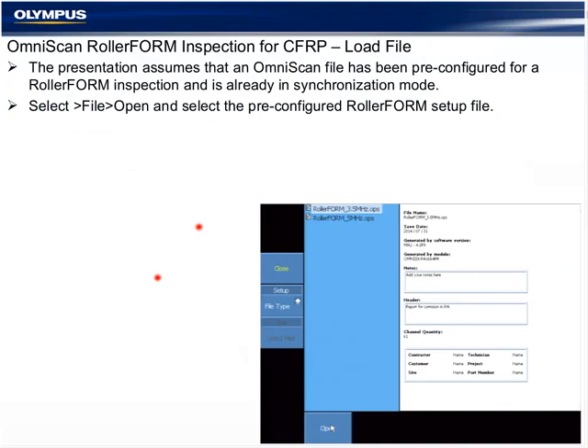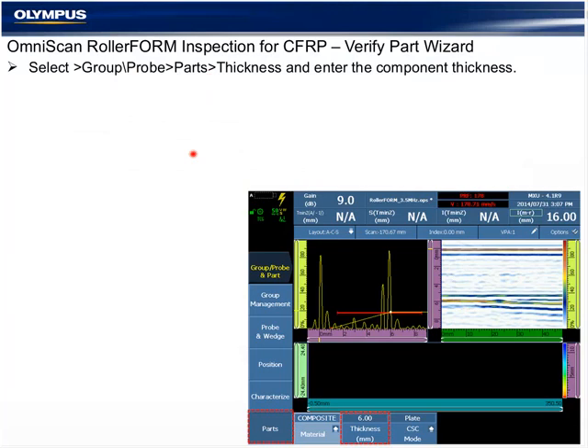Again, you're going to be provided default setup files with all of these parameters configured. This third presentation is designed to be used with either one of those files we've provided or the file you would have just created up to this point. On the OmniScan file name area, press and hold, or go to File, Open, and under the Setup filter we'll see the various setup files for the RollerFORM or the ones we've already created ourselves. We initially input the part thickness during the group wizard. This same parameter is available from the Group, Part menu, Part submenu. Enter thickness in millimeters or inches, depending on which mode the instrument is in.